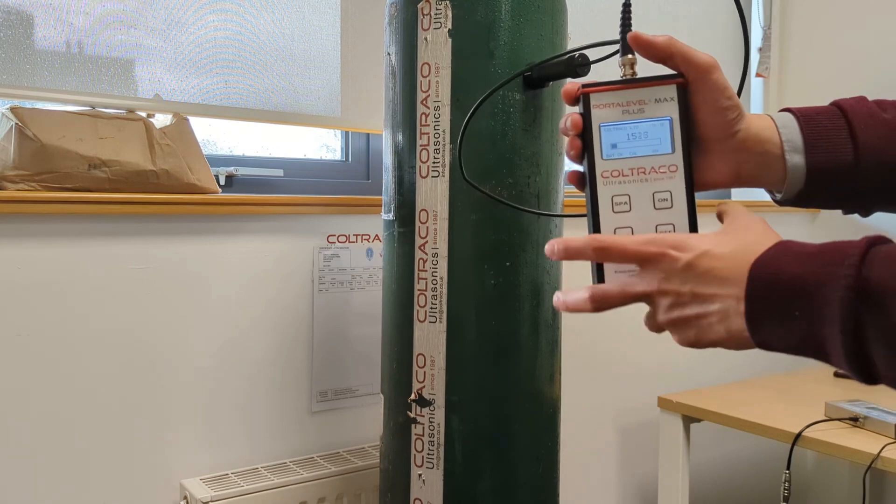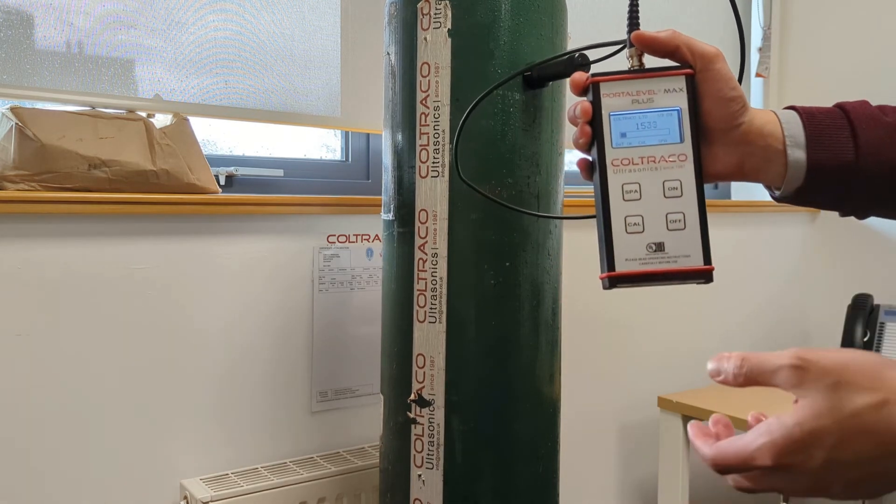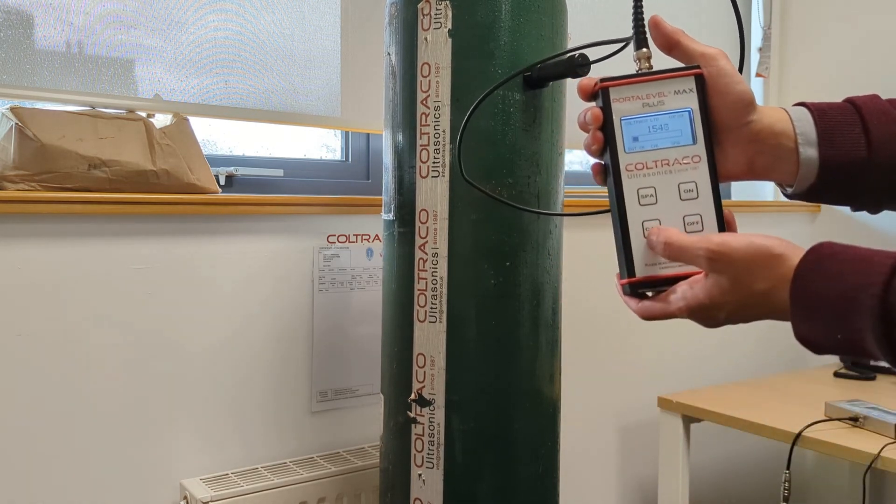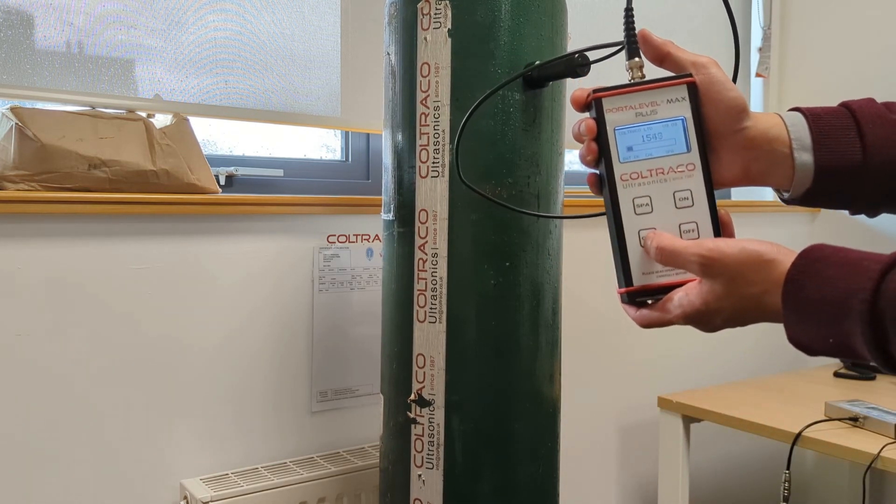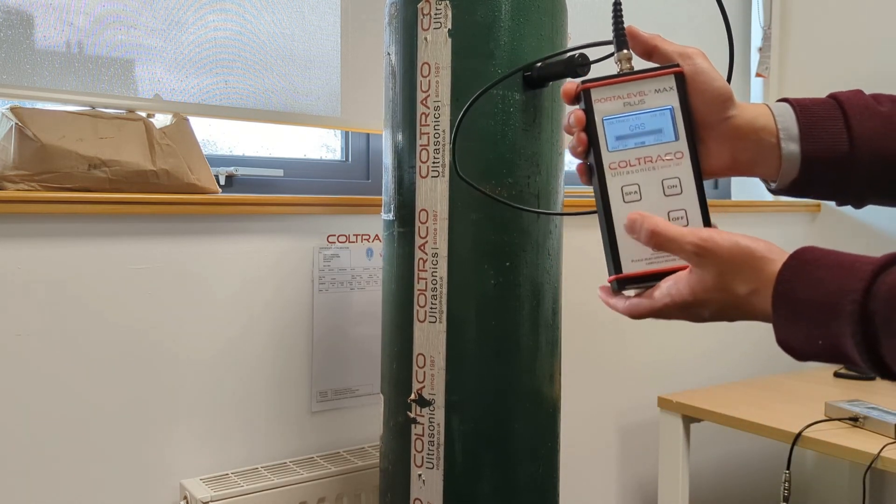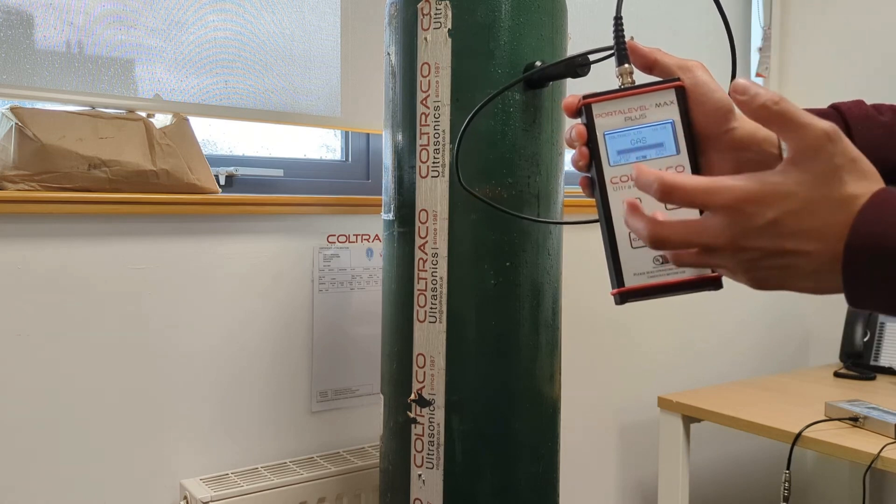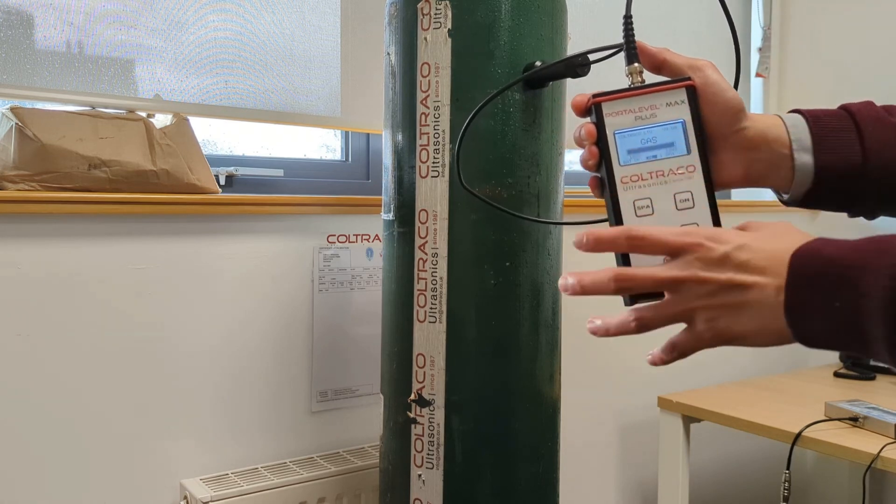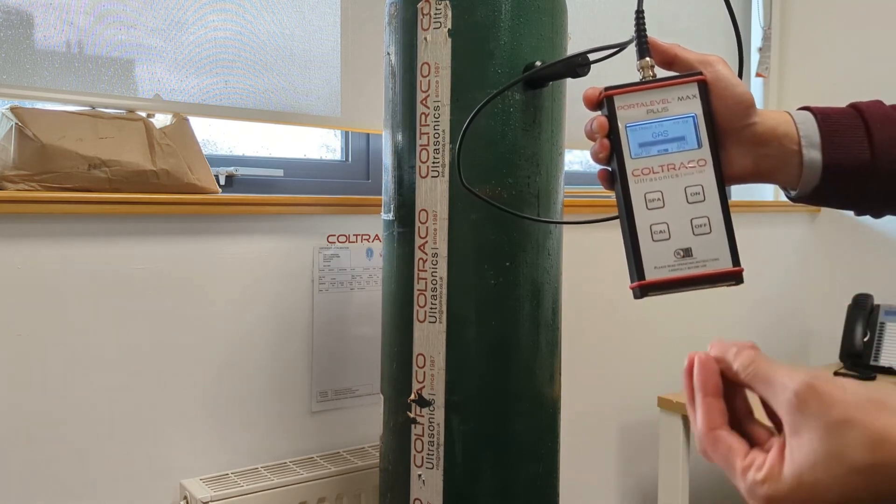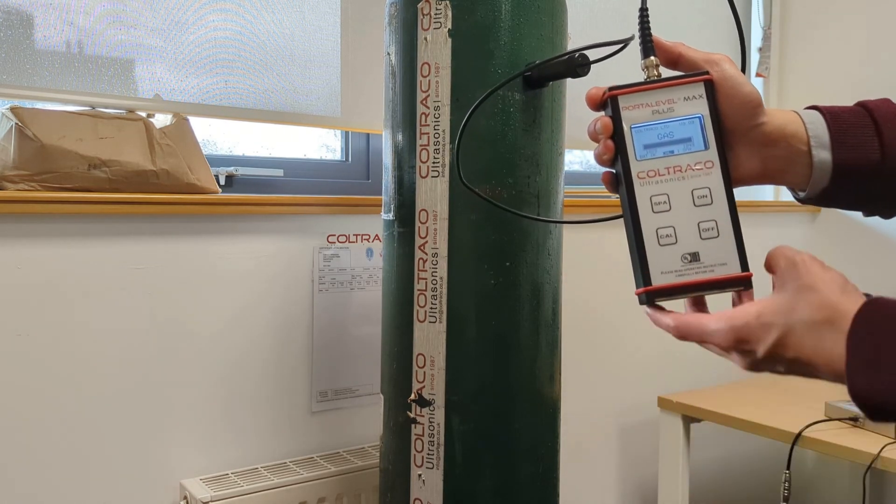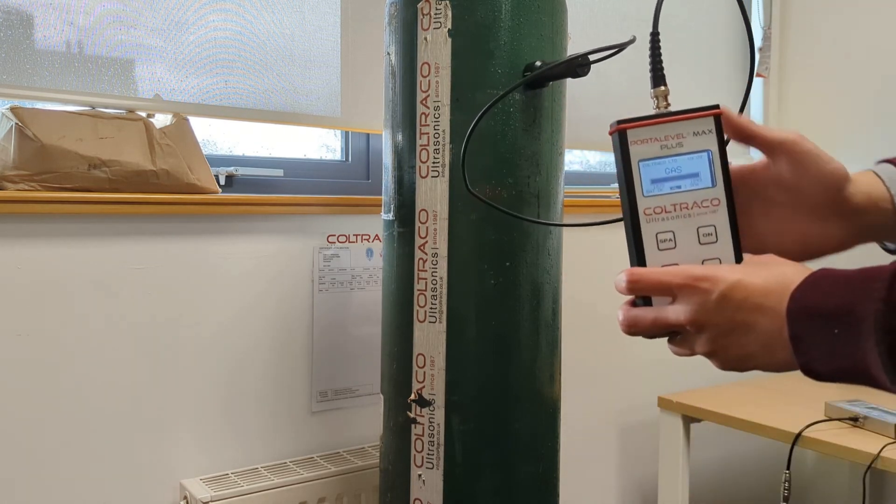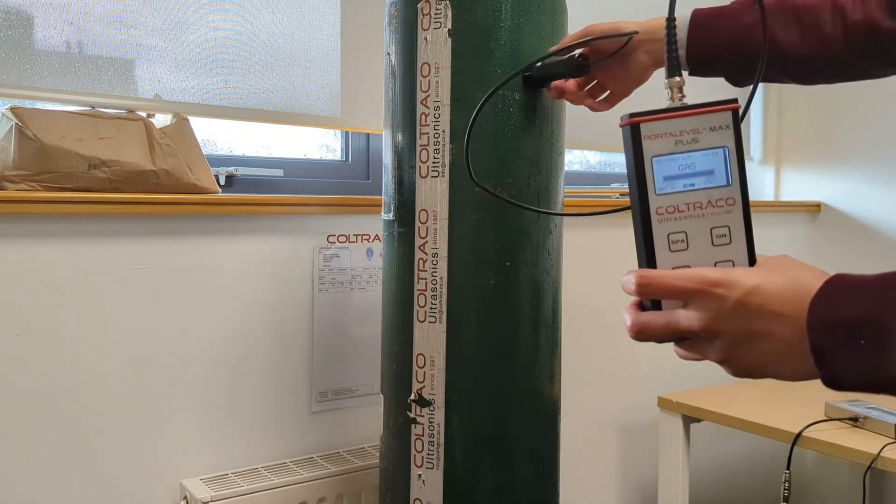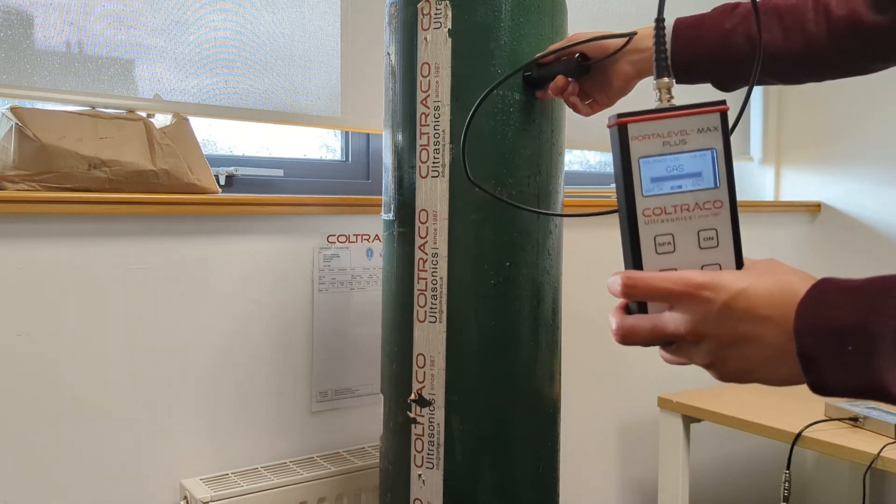This is what I believe to be a good average high reading for this instance. Press Cal and the digital reading would change to gas. Now move the sensor towards a position where it changes from gas to liquid to identify your liquid level.